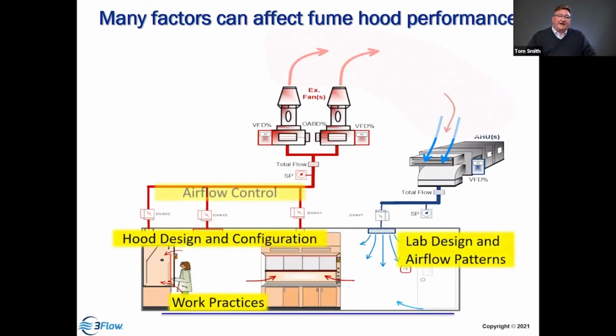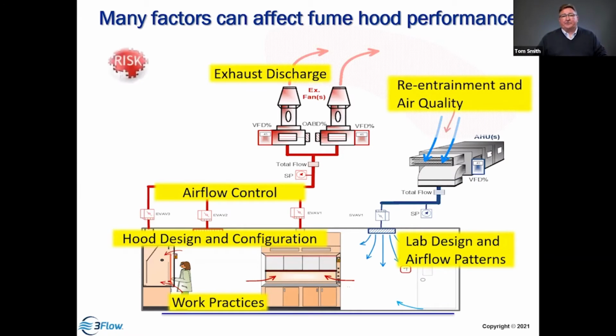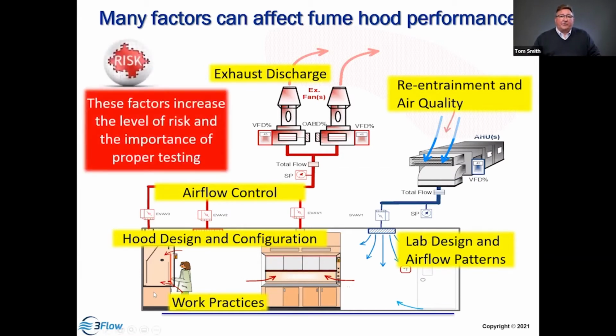So many factors can influence the containment capability of the hood. We have the work practices, we have the design and operation of the hood, we have the lab design, we have the airflow controls from minimum to maximum, we have the exhaust discharge, and the re-entrainment potential of bringing air back into the building that's contaminated. So when we're looking at hood testing, we need to evaluate all of these factors to make sure that we're achieving our objectives.